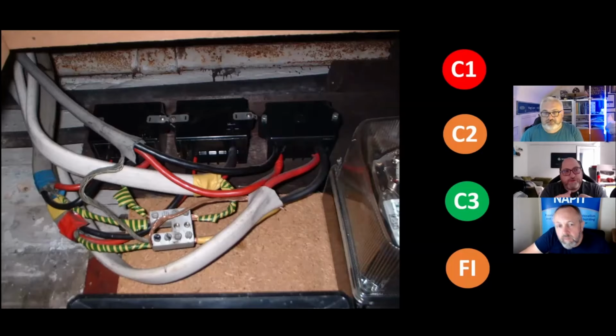So a couple of C2s there for me. Is it worth recording the C3s in this scenario, bearing in mind everything else is a C2? It's like the labelling, the safety electrical connection labels, not that. Well, you've got to put in what you see, but when you fix one of the C2s, you automatically fix the other one. For me, due diligence is listing everything you see, otherwise you could say well that's not quite right, you could apply mechanical protection, and then someone will say just put some boxing around it.